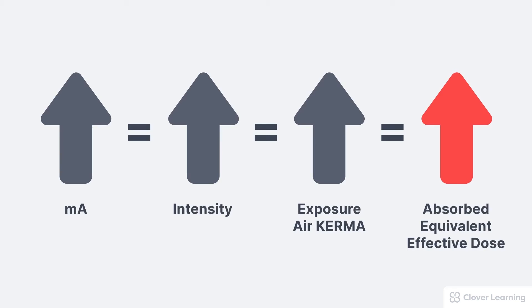Fortunately, most of these measurements are influenced in the same way by the same variables. For example, if we increase the mA and nothing else has changed, this is going to increase the beam intensity, which will then increase the exposure as well as the air kerma, and that's going to result in an increase in the absorbed dose, the equivalent dose, and the effective dose.